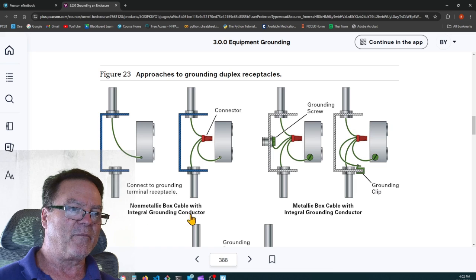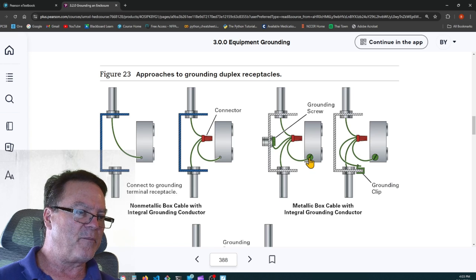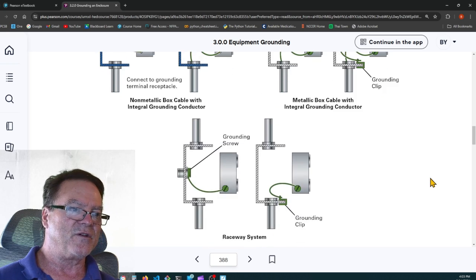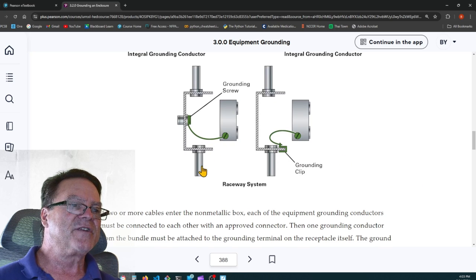If you have non-metallic boxes, you'll take your equipment ground to the receptacle, or if it continues on through the other conduit, you'll put a wire nut and make sure that all the equipment grounds are continuous and a pigtail goes to the receptacle. If it's a metallic box, you're going to ground the box as well as taking wires through the conduits and taking a pigtail to the receptacle. Or you can use the grounding clip on the edge of the metallic box. That's also fine. This one is using the conduit as the equipment ground.